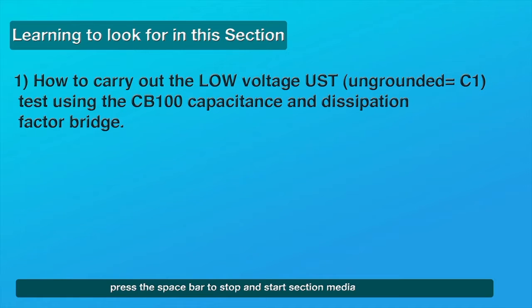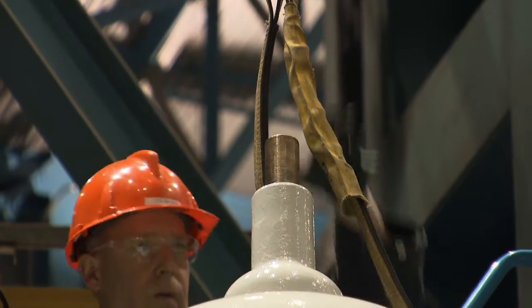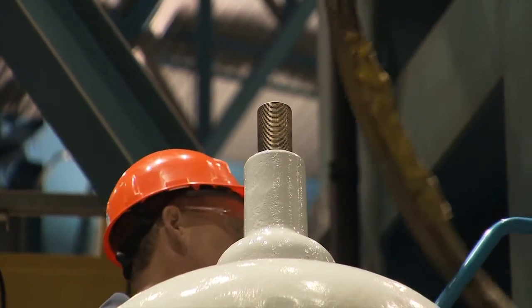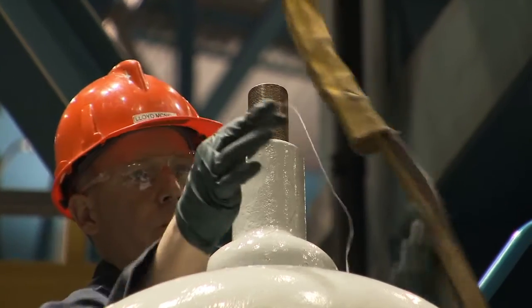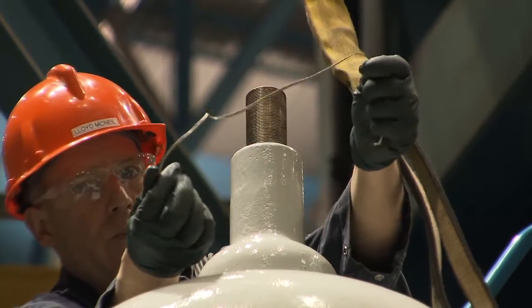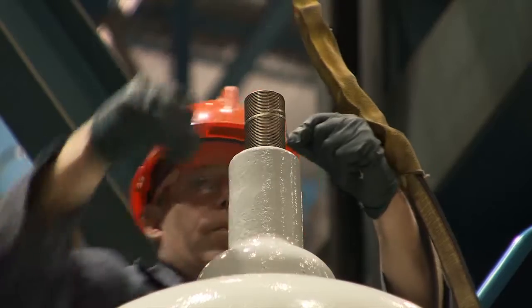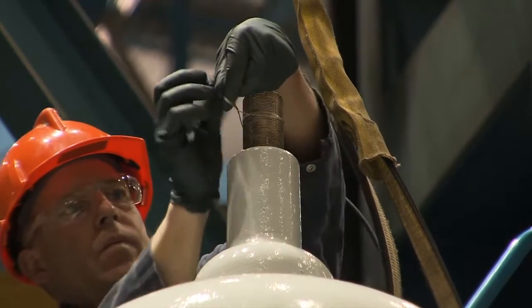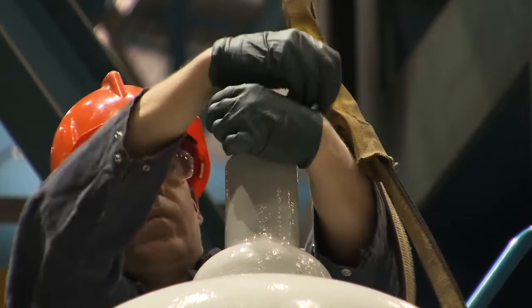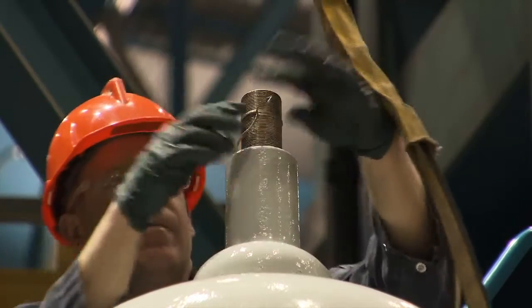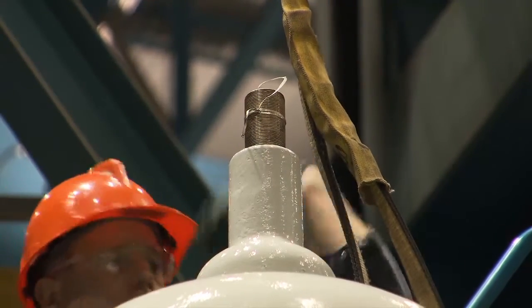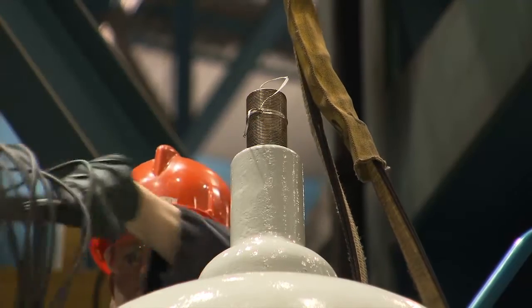The final Megger and low voltage UST electrical test for capacitance and dissipation factor. To facilitate adequate transmission, a strand of 1/8 inch bare copper conductor should be tied to the top of the terminal. The flexibility of concentrically stranded bare copper conductor makes it very suitable for uninsulated electrical connections. Loop a section of strand around the rod twice, and then twist tie the ends together so that a connection clamp can be easily attached.